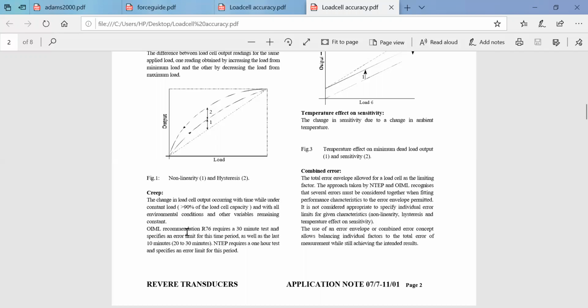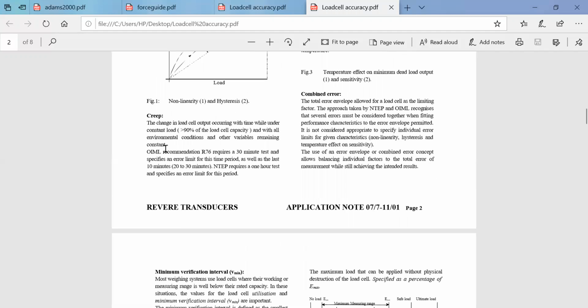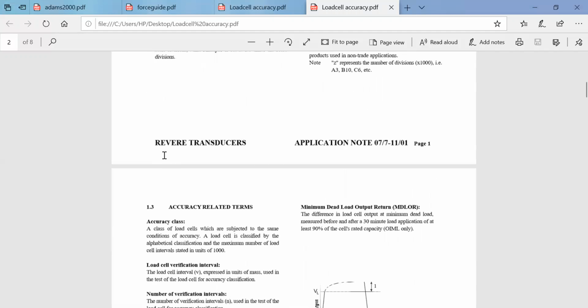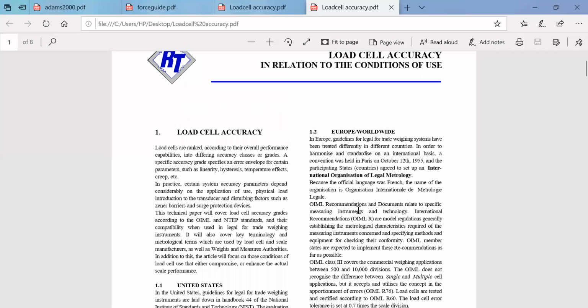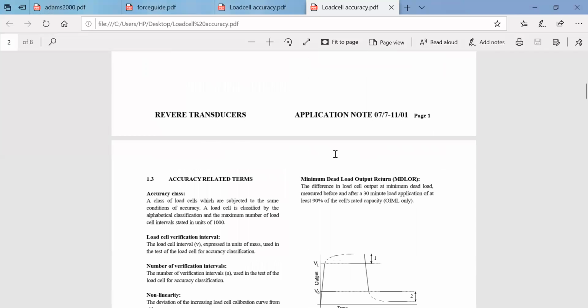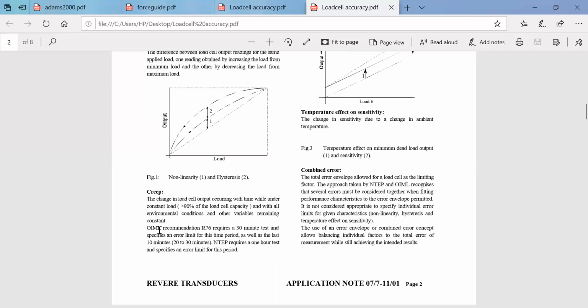What does the paper tell us exactly? Based on this, the OIML standard - OIML is with respect to our European standard, right? Based on OIML recommendation R76, it requires a 30-minute test, and then only it can specify an error limit for this time period. I told you, the dwell time here is nothing but 30 minutes. So you apply the load and wait for 30 minutes.